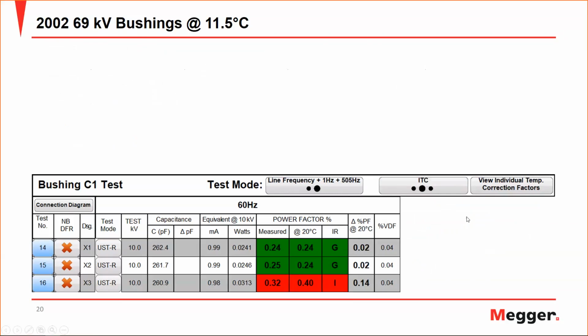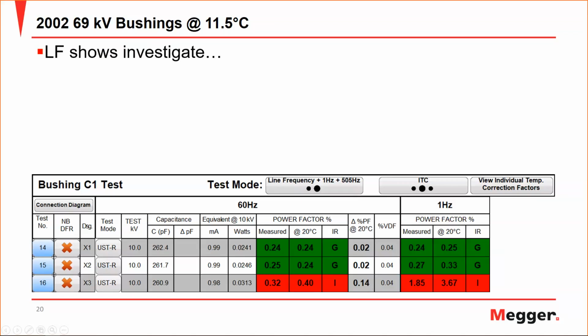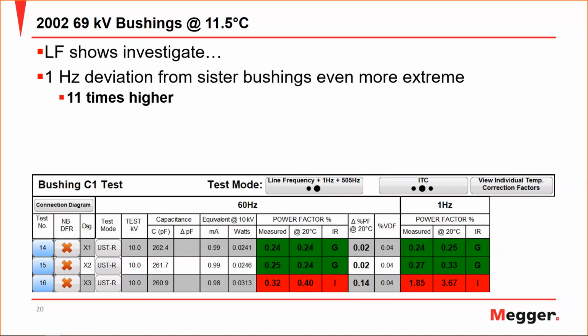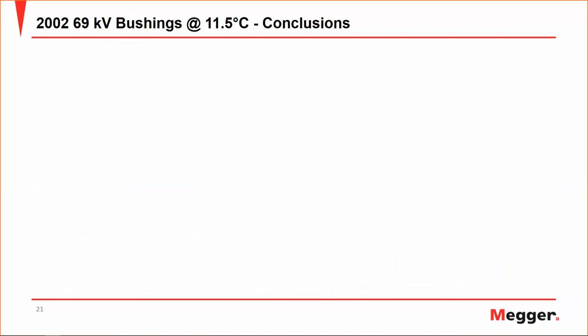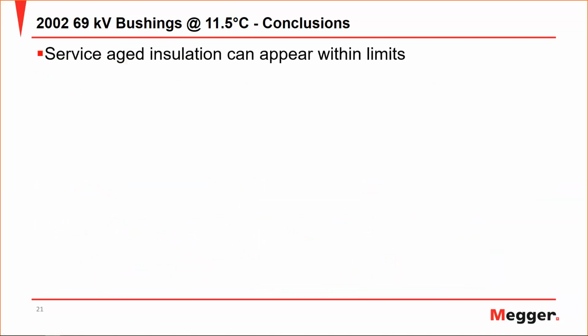So now if we look at ITC, we can see that the line frequency value is now showing investigate, where it's having a major deviation from the nameplate. And the 1 Hertz is now showing an 11 times difference than its sister bushings when properly corrected to 20 degrees C. So the conclusions from this one here is that service-aged insulation can appear within limits. We just saw that when we look at the X3 bushings, if we were only using temperature correction tables, we would have never been able to identify this change in a bushing, which it was obvious that it had changed when you started looking at 1 Hertz.